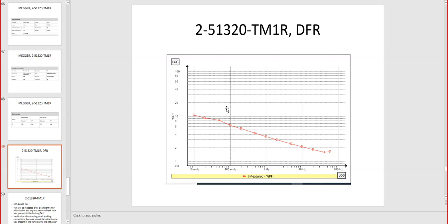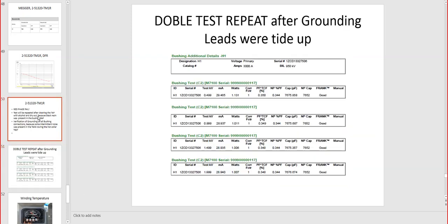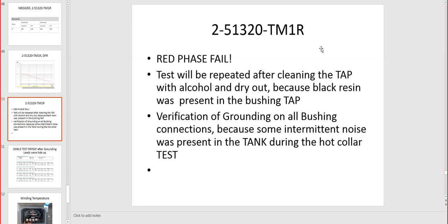When you have this kind of readings, you cannot do anything but repeat the test, try to correct the installation of the probes, and if you have two good readings after a bad reading, and you can explain why the bad reading happened, then you can actually apply power to the transformer. So this is the DFR for this bushing, and this is the actual conclusion on transformer 2. The red phase failed. Test will be repeated.